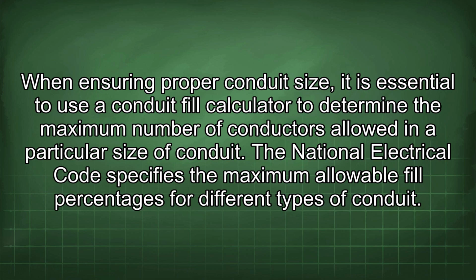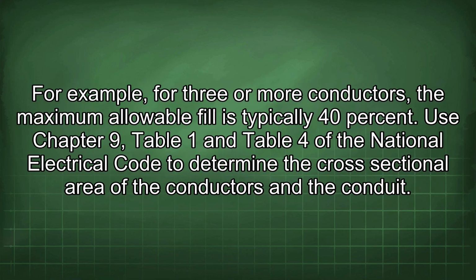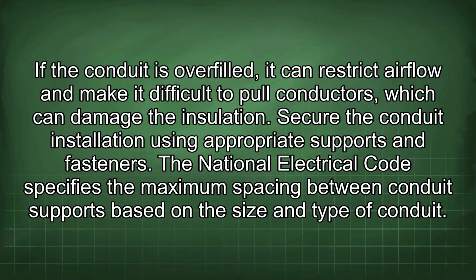The National Electrical Code specifies the maximum allowable fill percentages for different types of conduit. For example, for 3 or more conductors, the maximum allowable fill is typically 40%. Use Chapter 9, Table 1 and Table 4 of the National Electrical Code to determine the cross-sectional area of the conductors and the conduit. If the conduit is overfilled, it can restrict airflow and make it difficult to pull conductors, which can damage the insulation.